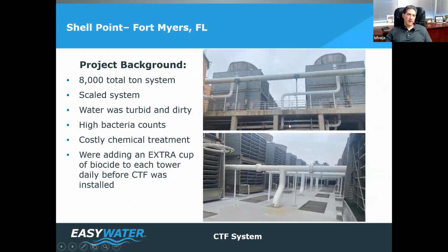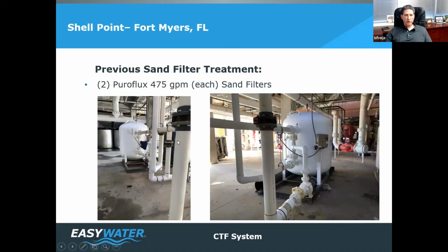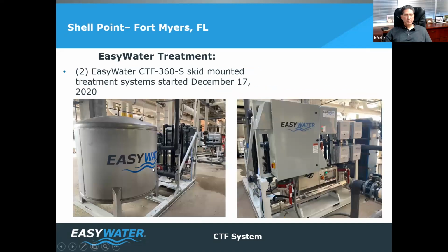Quick example, one of many: 8,000 tons of BAC cooling towers, excellent cooling towers. They already had sand filters and sump sweepers, and a very good chemical company. But every year, scaling on the fill, scaling in the condenser tubes, high bacteria counts, lots of expensive chemicals. Paul Bertonis, the chief engineer, who's still the chief engineer, was unhappy with the results and how much money he was spending. He already had two 475 gallon per minute Puroflux sand filters. He removed these and put in their place two of our skid mounted CTF systems, started up December of 2020.